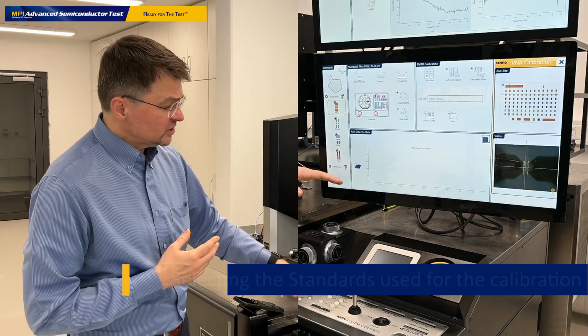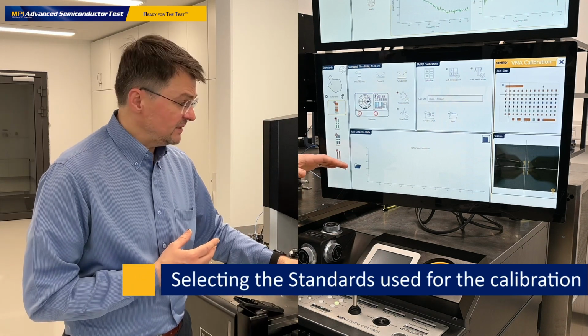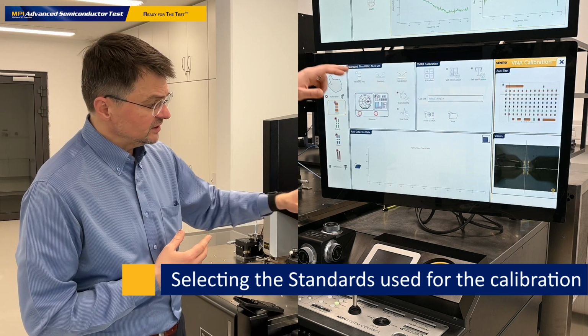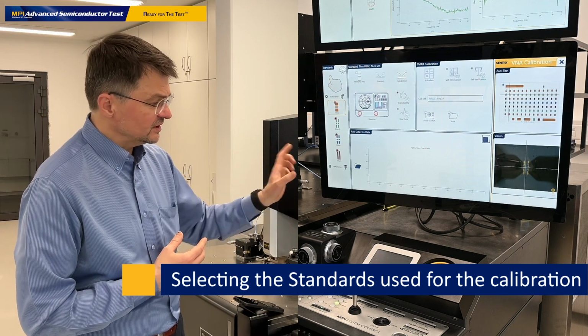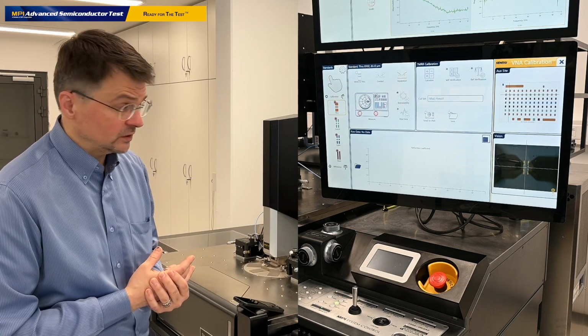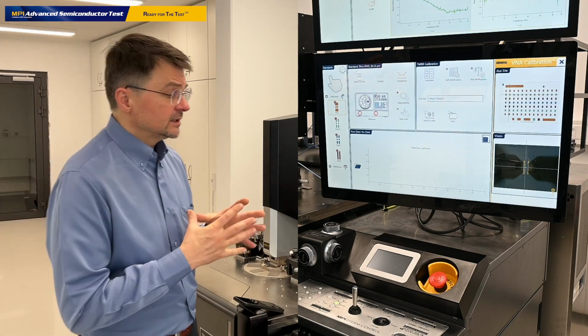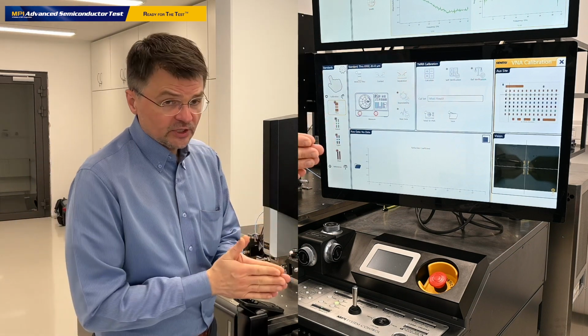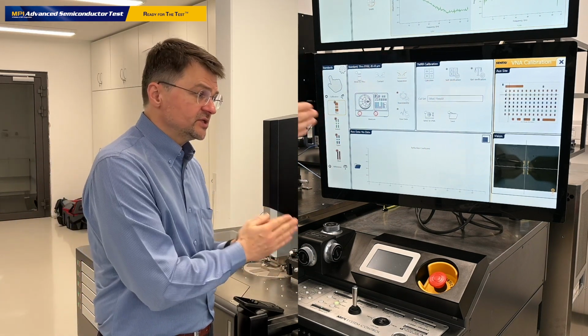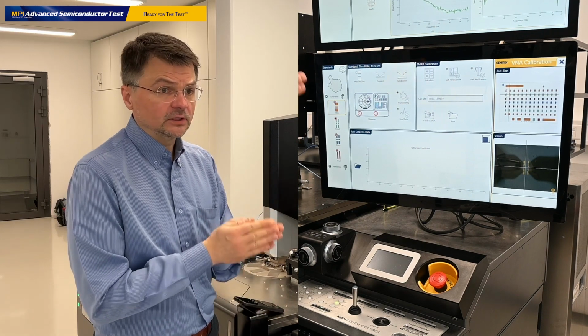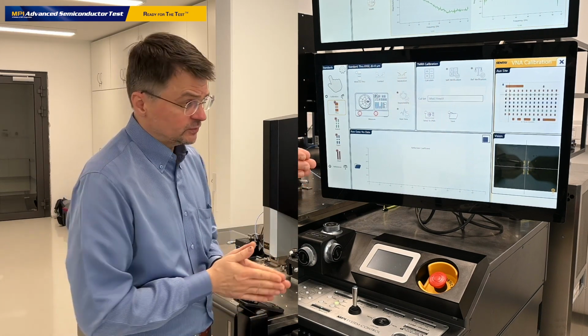So, the calibration procedure is currently configured in the manual mode. That's what we can see here and read from the screen. It's just a finger icon, meaning that the calibration process will be executed manually. And before I go and measure calibration standards, I really would like to tell the system which standards I think are good to be used for the calibration process.